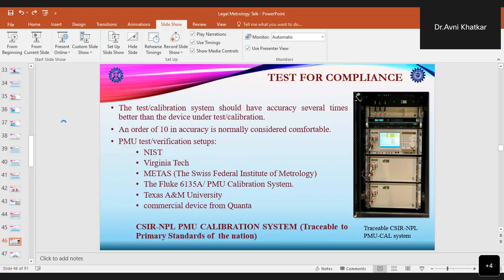that is the Swiss Federal Institute of Metrology, and the Fluke 6135A PMU calibration system. And there are some other facilities also, including those at Texas A&M University and a commercial device from Quanta. Of these setups, those at NIST and METAS are static systems. That is, they are fixed at their host locations to which devices must travel to be tested.